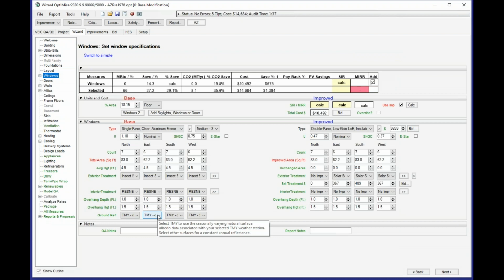I had not usually thought of window upgrades as a winner in most circumstances, and it's still a very high cost measure for the payoff. But in terms of making these pre-cooling strategies work, it was a surprise to me to find out that doing everything else didn't get you far enough. That the heat gain, the conductive heat gain through the windows was such a big factor.